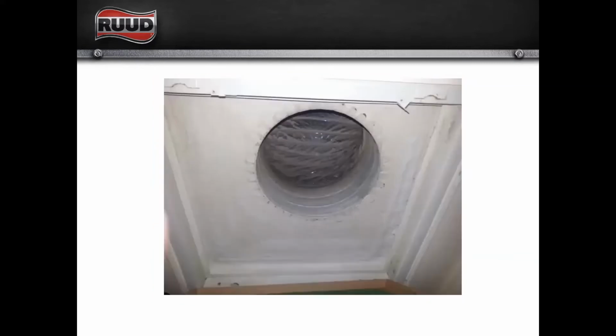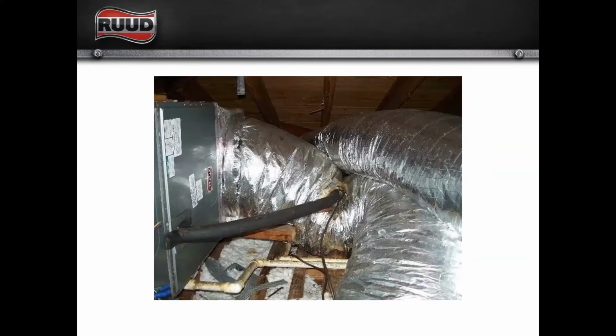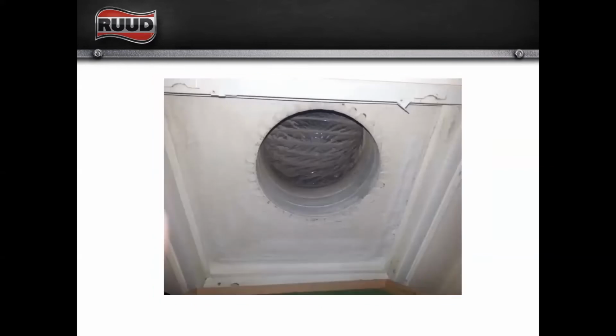Sometimes they're a little bit harder to see. This one here is pretty obvious, right? You look at this air handler and we've got a ductwork problem. You might not find something like this, where I don't know how obvious it is, but we have a filter grill here, and on the back side of this filter grill, our flex is pulled down so tight at sort of a 90-degree angle that we're really not moving any air through this return. And you might not notice this until you take the grill off, pull the filter out, and really start looking around.